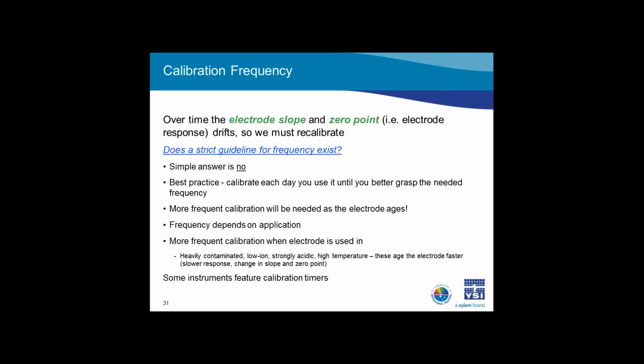I suggest, as a best practice, start by calibrating the system every day you use it. If you find, for example, that you are using the system every day and the sensor is holding its calibration adequately for 2 or 3 days, then you yourself may decide to only calibrate every 3 days. Another example would be if you're only using the instrument once per week. In that case, I would definitely perform a calibration before each use. Generally, a new electrode could hold its calibration for a week or more, while an aged electrode may drift out of calibration within 24 hours. If you are worried about forgetting to recalibrate, look for an instrument that provides a recalibration prompt or timer based on user-selected criteria. This can help remind you when it's time to recalibrate your system.